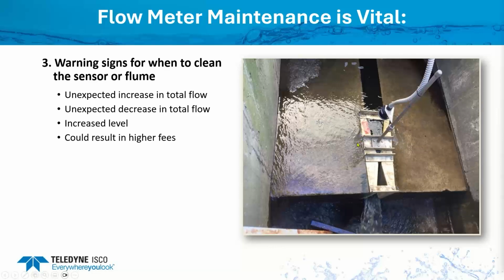Now, as far as where this is going to save you some money, if you catch this soon enough, you're going to have accurate flow readings. In this case here, it's calculating flow based off the 100% full flume, which is in a surcharge condition, which is then over-calculating your flow. So if you're billing on it, now you're over-billing, because you're incorrectly calculating the flow going through there, when in reality you only have a couple hundred gallons per minute, but based on the flow table, it's showing you that it's maybe 1,000 or 2,000 gallons per minute.